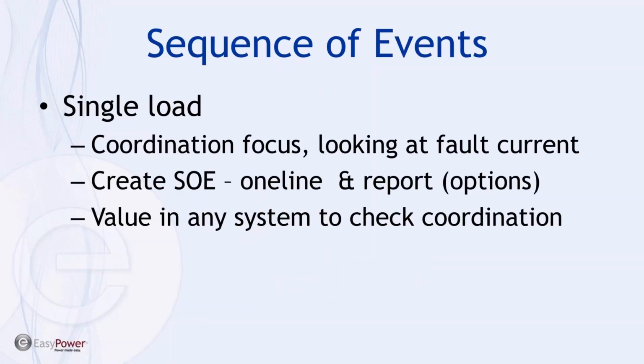Now, sequence of events is a feature that's built into EasyPower that, again, is not that well understood or regarded, but I find it's extremely valuable in a number of applications. For instance, one that jumped out at me early on was when you have, say, renewable energy designs with photovoltaic sources that don't turn off on a fault, and people end up trying to adjust their incident energy by a relay on the utility and not understanding why it didn't change. And sequence of events just very quickly pointed out that the problem was there was no control over the PV contribution. So there's a lot of places where it's a good place to start.